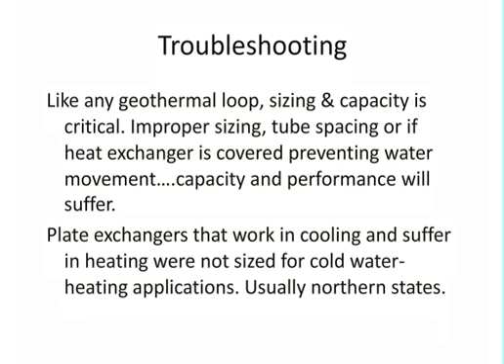Plate heat exchangers that work in cooling and suffer in heating, they just don't perform well during the winter. Well, they're typically not sized for the cold water heating application. Again, usually in the northern climate states. Again, you've got to make sure that you're applying the correct size of plate or tube style heat exchanger for that water condition, that temperature of water. You want to make sure that whatever you put in is sized for that dominant load, whatever that happens to be for your location.